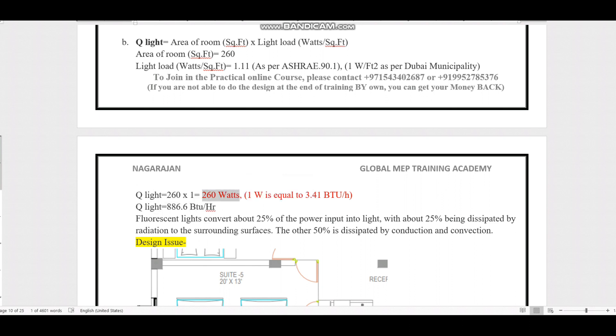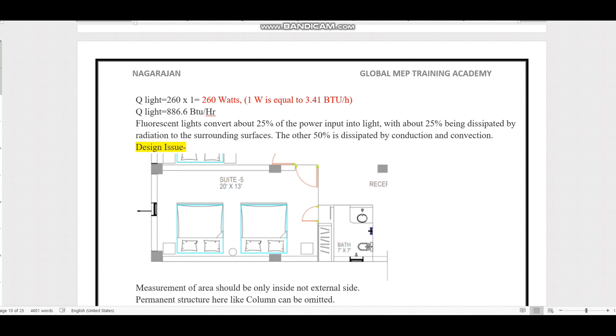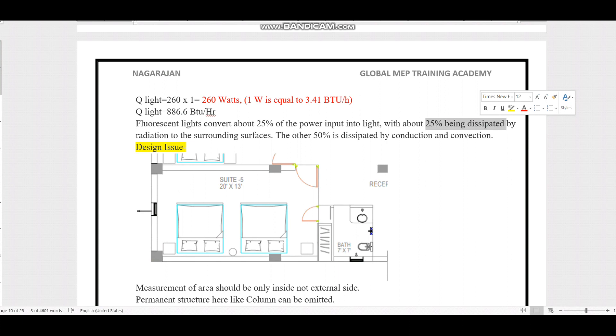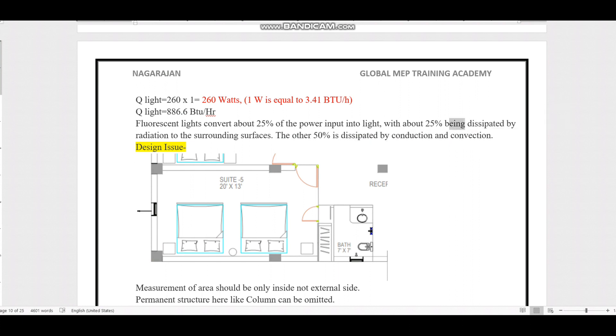Fluorescent lights convert about 25% of power input to light; approximately 25% is dissipated as radiation and 50% by conduction and convection to the surrounding space. As a mechanical engineer, our concern is the heat dissipation — the heat load from appliances and lighting — not the electrical power input. That heat dissipation is what contributes to our cooling load calculation.